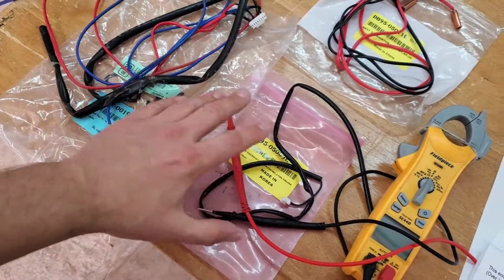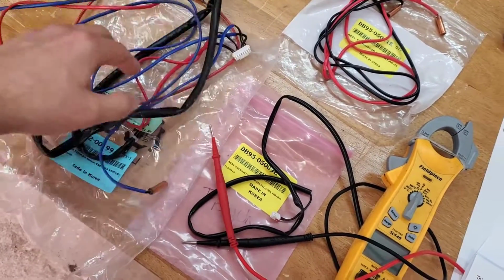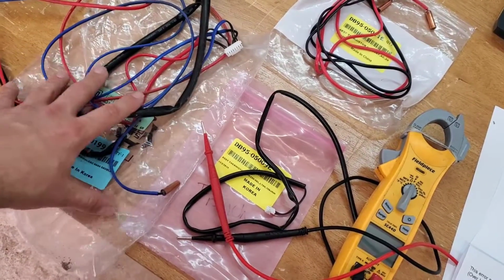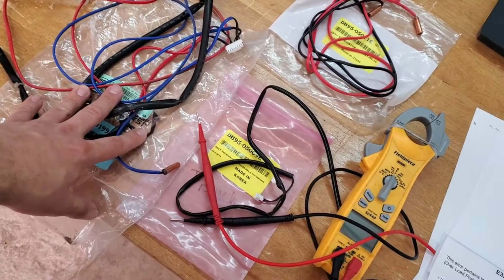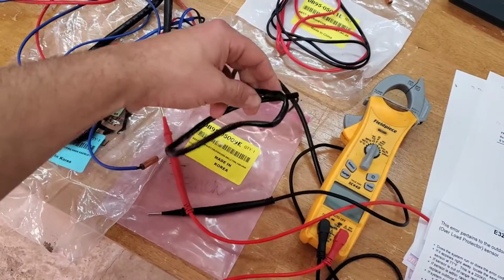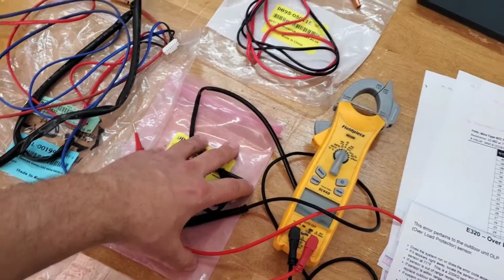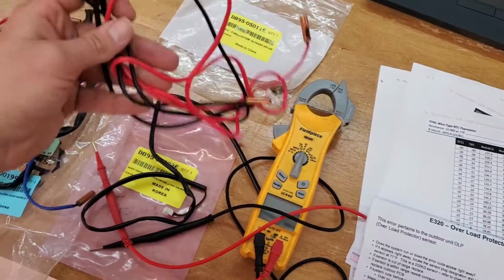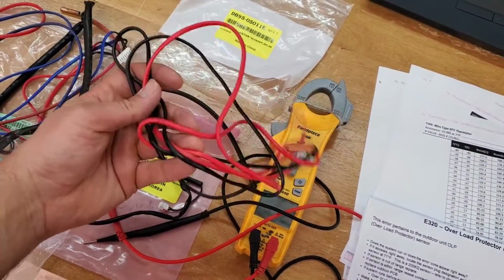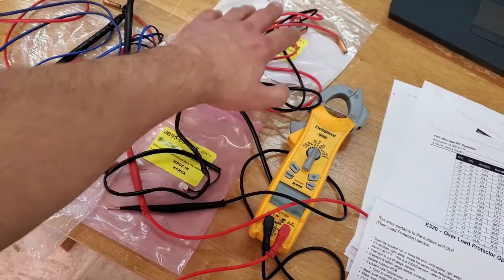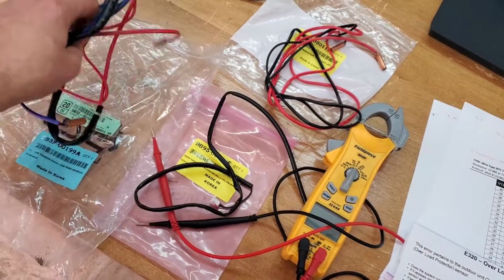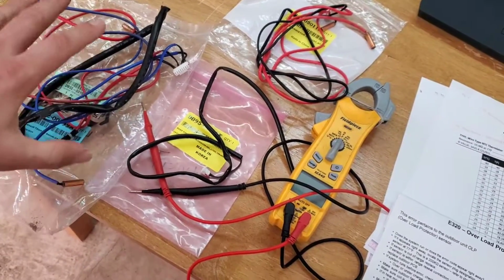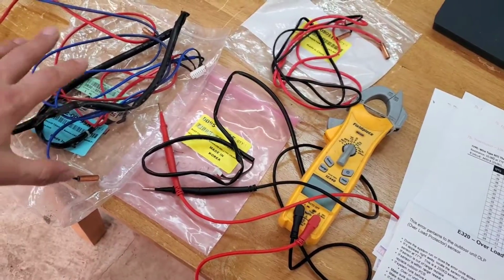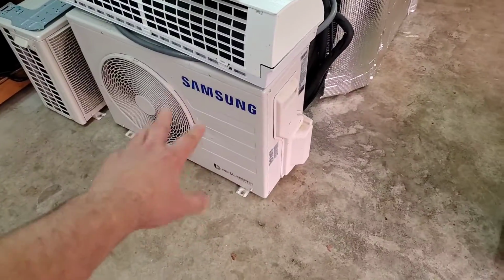All right, so before we talk about the error code, I want to show you this right here is the plug and sensors for the outdoor unit. This includes the OLP sensor. Then we've got an indoor air sensor. This is off a ducted air handler. And then we've got an EVA inlet and outlet. This is on the indoor heat exchanger of a ducted Samsung. So we've got these 10 kilo ohm sensors, and then we've got this 200 kilo ohm sensor, the OLP, which we're going to talk about in just a minute. So I just want to show you that's where the OLP will be located in the outdoor unit.